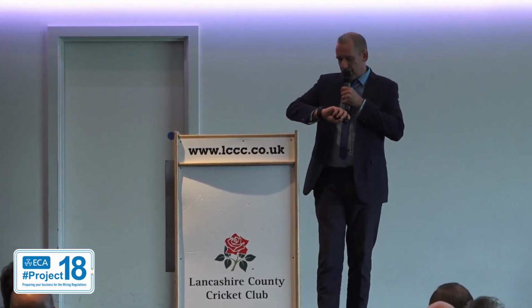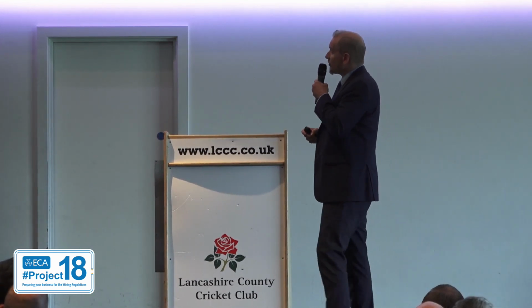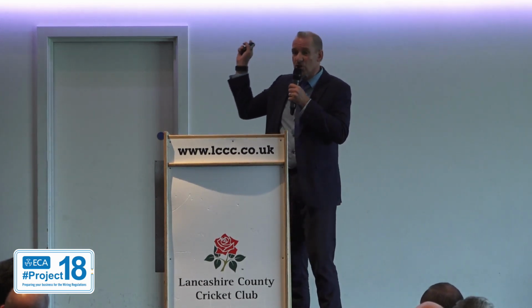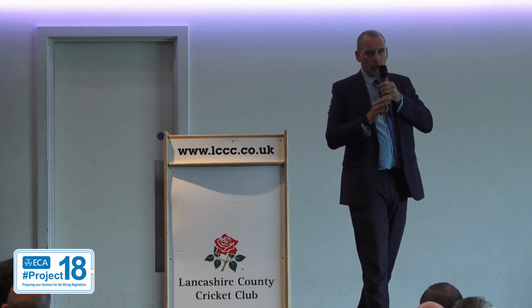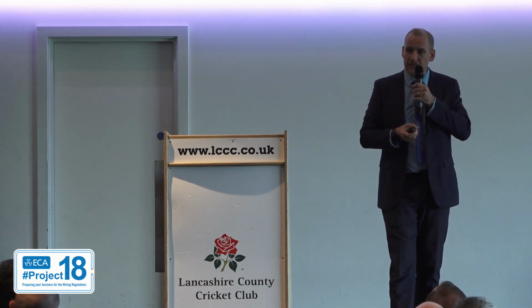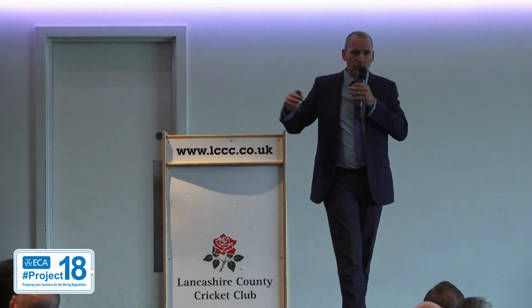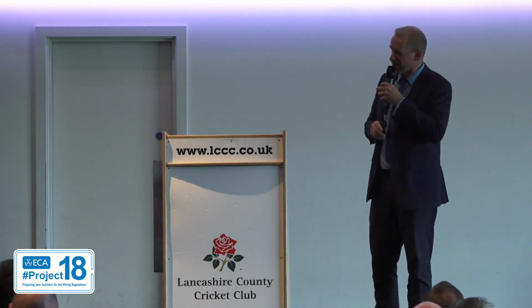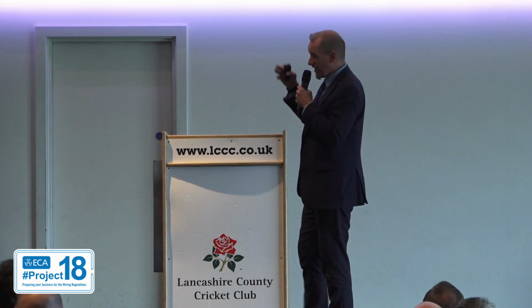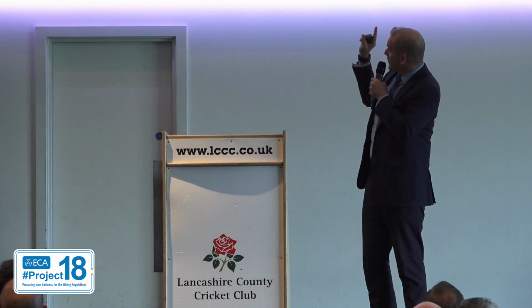So that is the three sections. Obviously, as I said before, and I say it again, chapter 52 here, this is a significant change. So it's moving away, where at all possible, at all times really, from using plastics as a sole means of support. So you still can use plastic, but you must intersperse it with metalwork. So you can't use plastics as a sole means, as I say. Significant change. So if we take anything from this 15 minutes I've just spent up here talking to you about this, just remember this. Chapter 52, significant change.